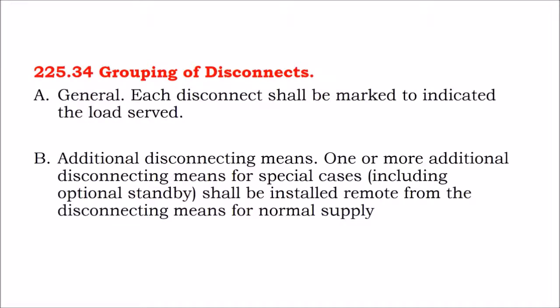So then we get to the grouping of the disconnects, and this is one that stuck out at me. Each disconnect should be marked, and then they need to be grouped. So those 6 disconnect switches, whether it's 6 breakers on a panel or 6 individual knife switches with their individual fuses, they have to be grouped together in the same location. And so you can't just have 3 microinverter circuits on a panel and 3 microinverter circuits on a panel on the other side of the building, both coming in to lug onto the utility meter inside the main service panel. They would have to be on their individual disconnect switches right by the main service panel, no more than 6 of them.